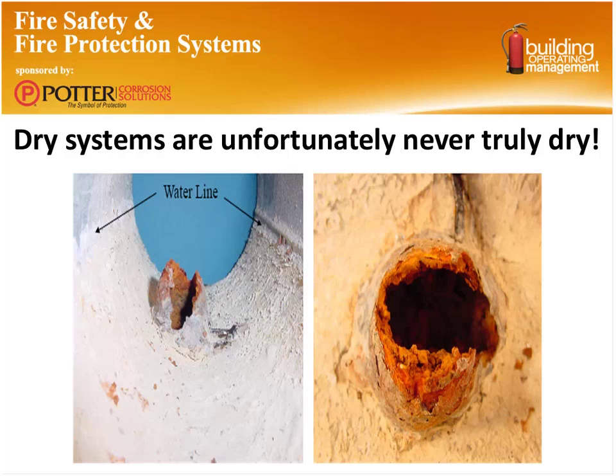I always like to say these pictures look like something from a bad horror movie. I don't want to open up a pipe and see one of those staring back at me. I have some fear of some Sigourney Weaver movie where something jumped out of a person. But it happens. These little nodules are spots where corrosion has happened. In time, it will breach the surface of the pipe and you will get a leak.